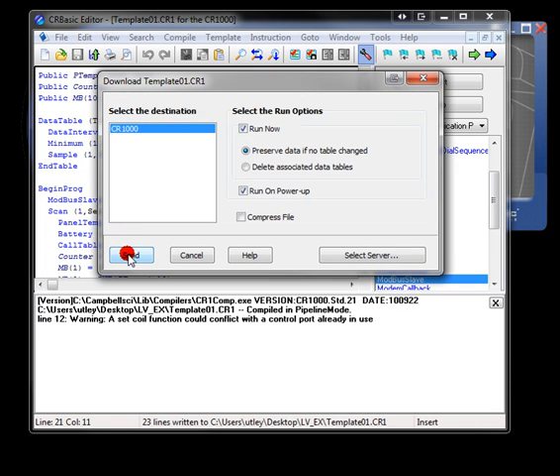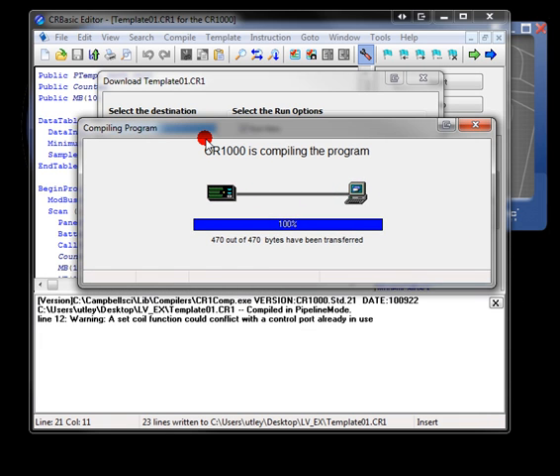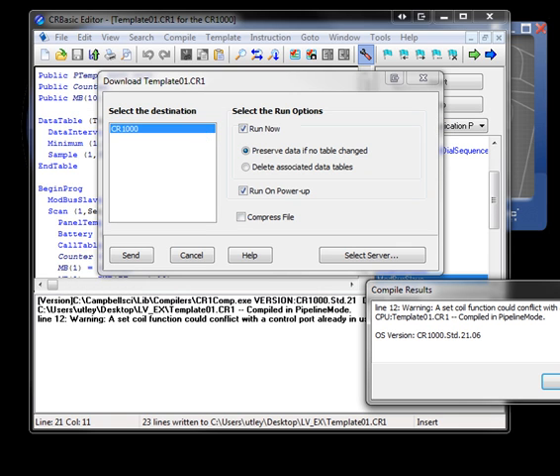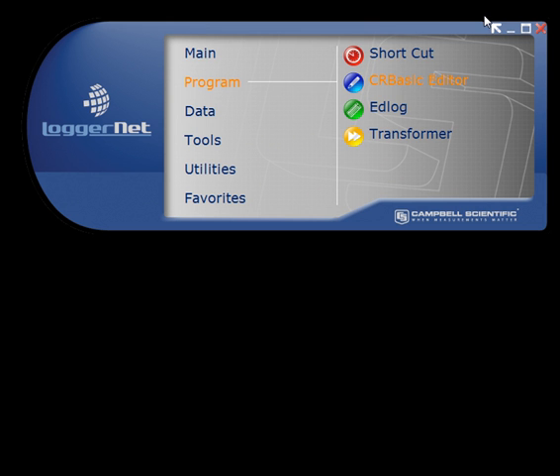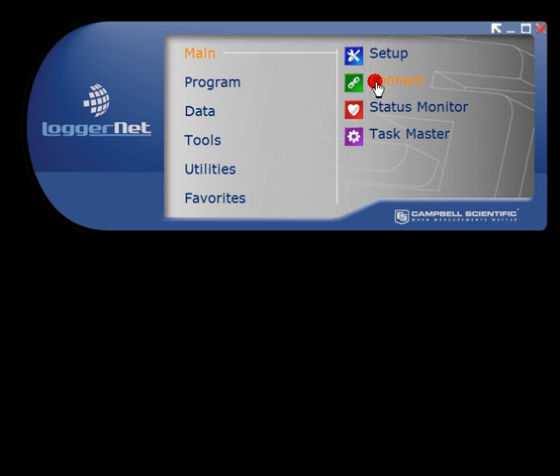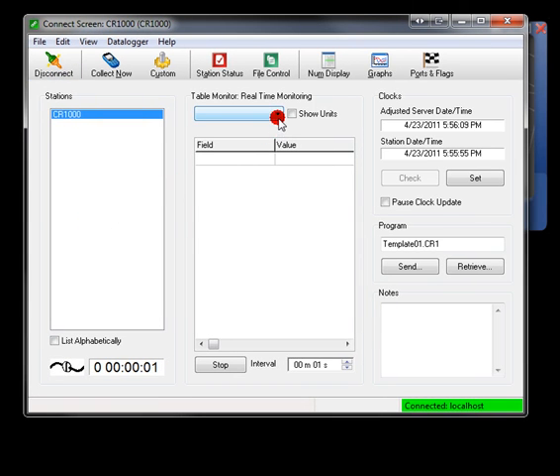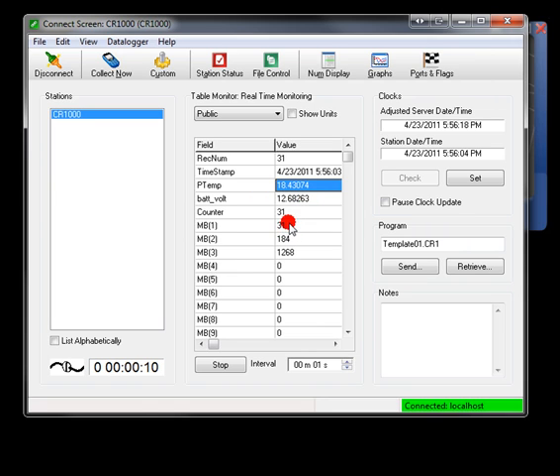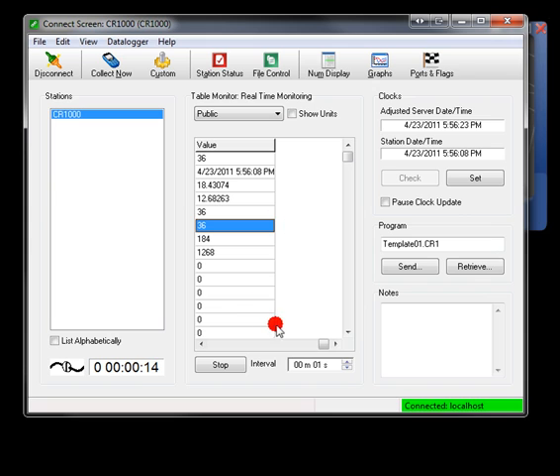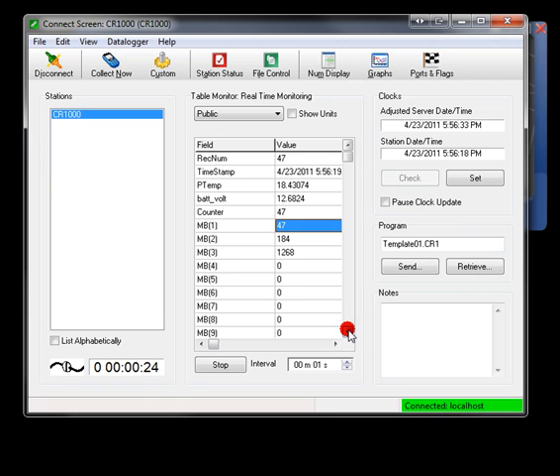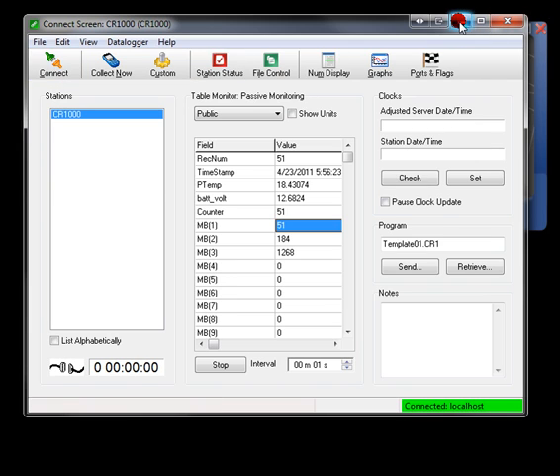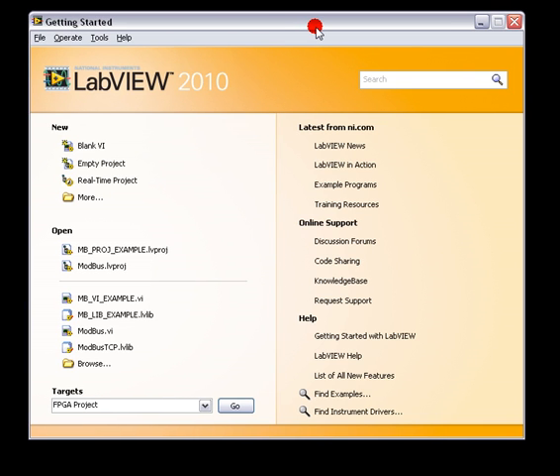So we're going to actually save, compile, and send this to our data logger, which is connected to my local area network. The data logger can communicate using PakBus over IP, Modbus TCP, HTTP, email, FTP - a wide variety of communication protocols, all at the same time. It's not a one or the other type situation. We're going to just real quickly use the connect screen to check up on our data logger, make sure everything looks good. So we'll look at the public table. We see our panel temperature, 18 degrees Celsius. Our battery voltage is 12.6. Our counter is incrementing as expected. And our Modbus registers are updating as expected here. 184 for 18.4 degrees. 1268 for 12.68 volts.